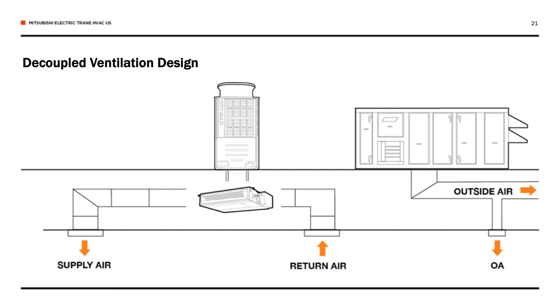Those pieces of equipment, energy recovery ventilators and dedicated outdoor air systems, have several ways of communicating. Many industry standard manufacturers would use the same communication protocol as the VRF equipment, and integration in that situation is very easy. A third-party dedicated outdoor air system might be integrated with a simple input-output configuration, or it might come with a BACnet card that makes most of the communication available over software rather than hardwired points. This can save a lot of integration time and a lot of actual physical labor on the job site as well.